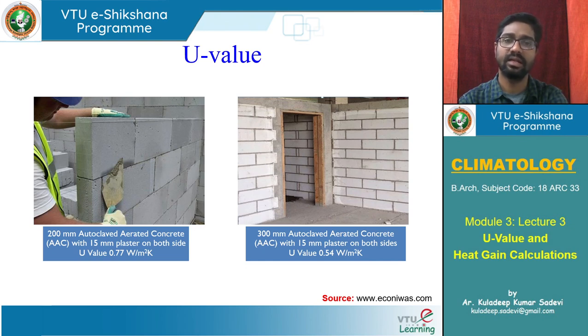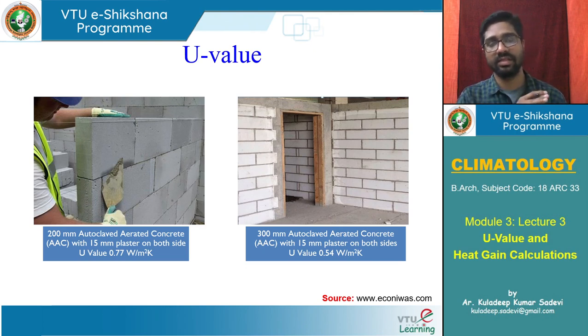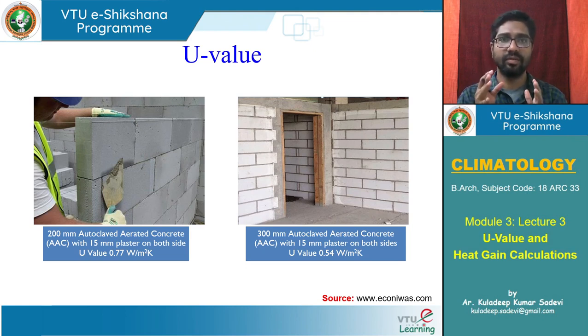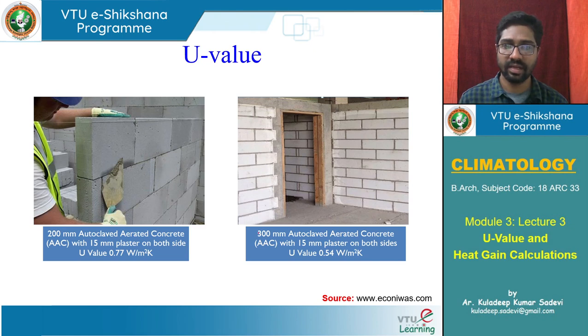The first case is a 200 mm thick wall of AAC blocks, the second case is a 300 mm thick wall of AAC blocks. The 300 mm thick wall should have lesser U-value, because a thicker wall offers more resistance, so heat flow will be lesser. The thicker the wall, the lesser the U-value.